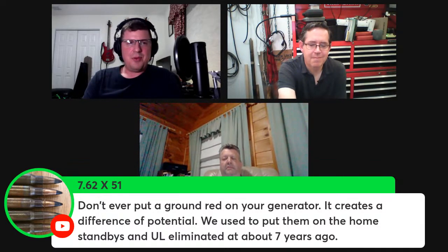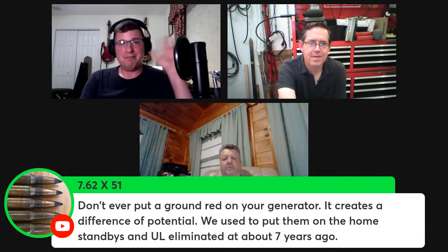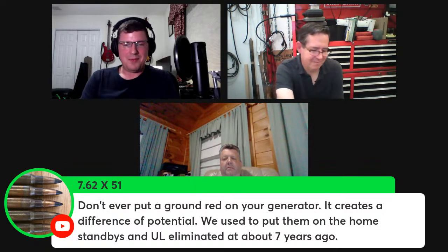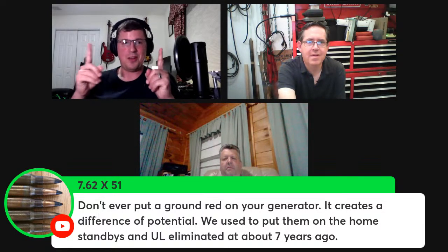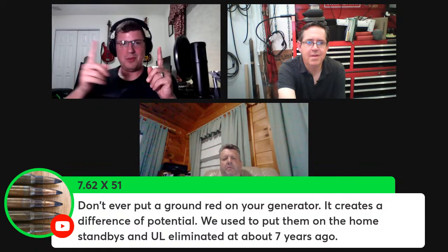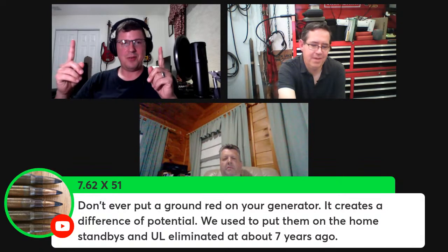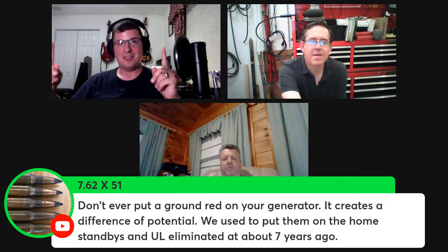The 7.62 by 51 comment brings up a good point—again, this isn't my area of expertise, nor mine, so I default to people with more experience here. He's saying that putting a ground rod on your generator creates a difference in potential between the two ground rods, one at your main panel and one at your generator. So the greater the distance between the two ground rods, the more potential there can be.